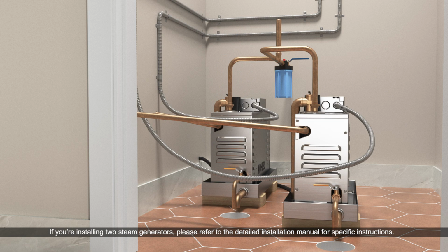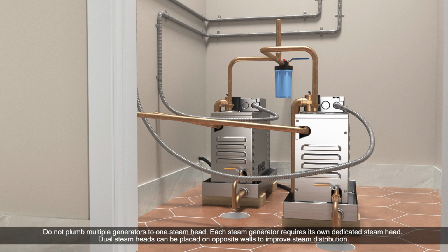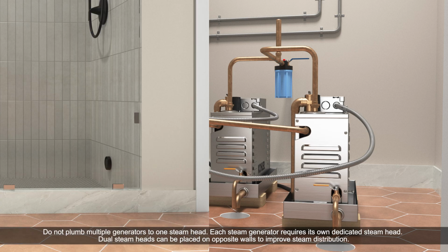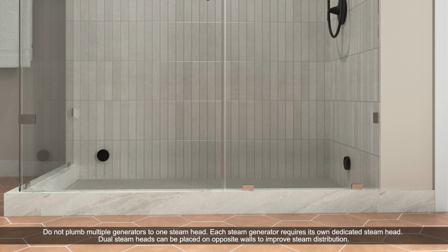If you're installing 2 steam generators, please refer to the detailed installation manual for specific instructions. Do not plumb multiple generators to one steam head. Each steam generator requires its own dedicated steam head. Dual steam heads can be placed on opposite walls to improve steam distribution.